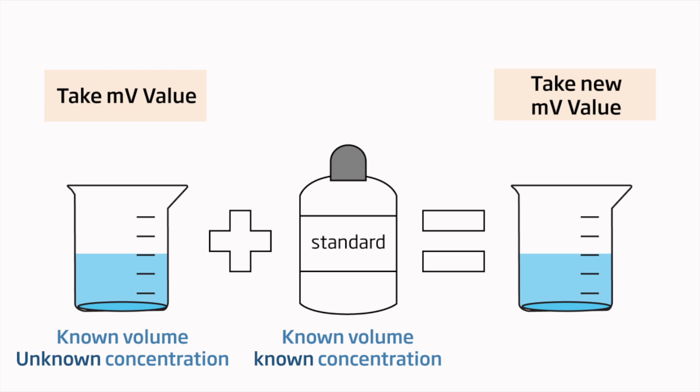An incremental method is a spiking technique that increases or decreases a sample concentration. This technique is usually used for samples with extremely high or low concentrations that would otherwise be too difficult to obtain an accurate reading due to the limits of the electrode's optimal measurement range. Additionally, incremental methods typically produce results that are more accurate and repeatable than those obtained from a direct measurement.